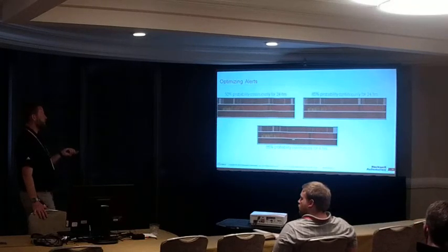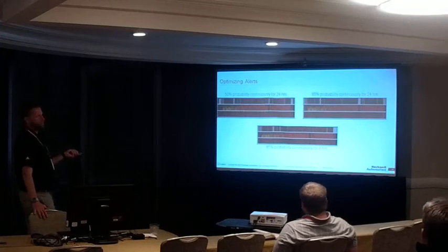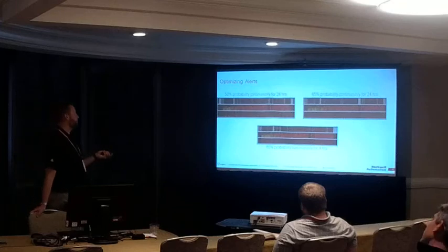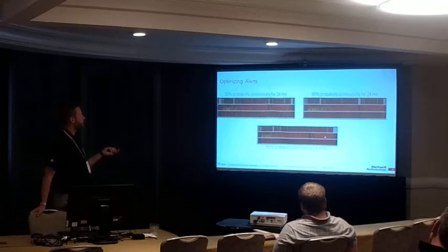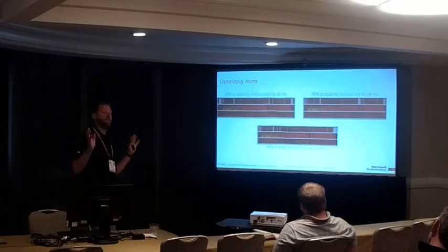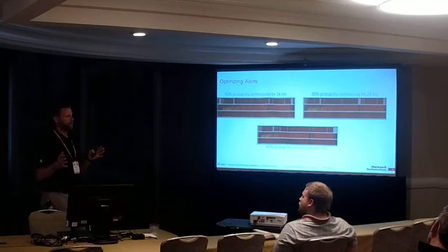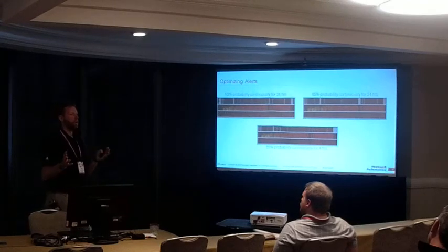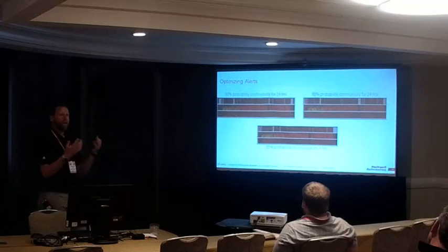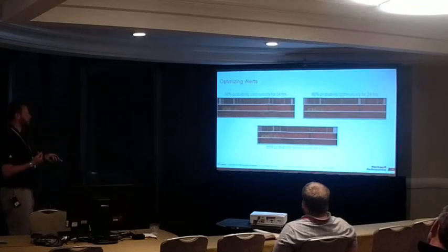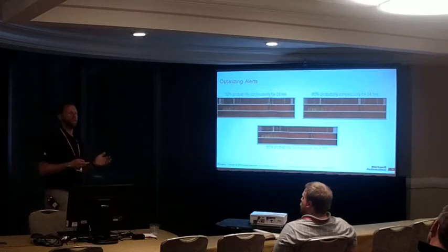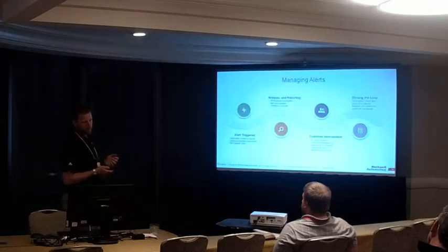So we then talked it through and said, all right, 85% probability, but continuous for 4 hours. We've reduced the amount of time we need to see an alert. Now we've got a very consistent alert, and it's out about 10 days, which the customer said is the right amount of time to plan their maintenance activity to pull that cylinder out and put in a new one. So we're playing with the tool set to get the right outcome for the customer based on their evaluation of what they need and how they need it.